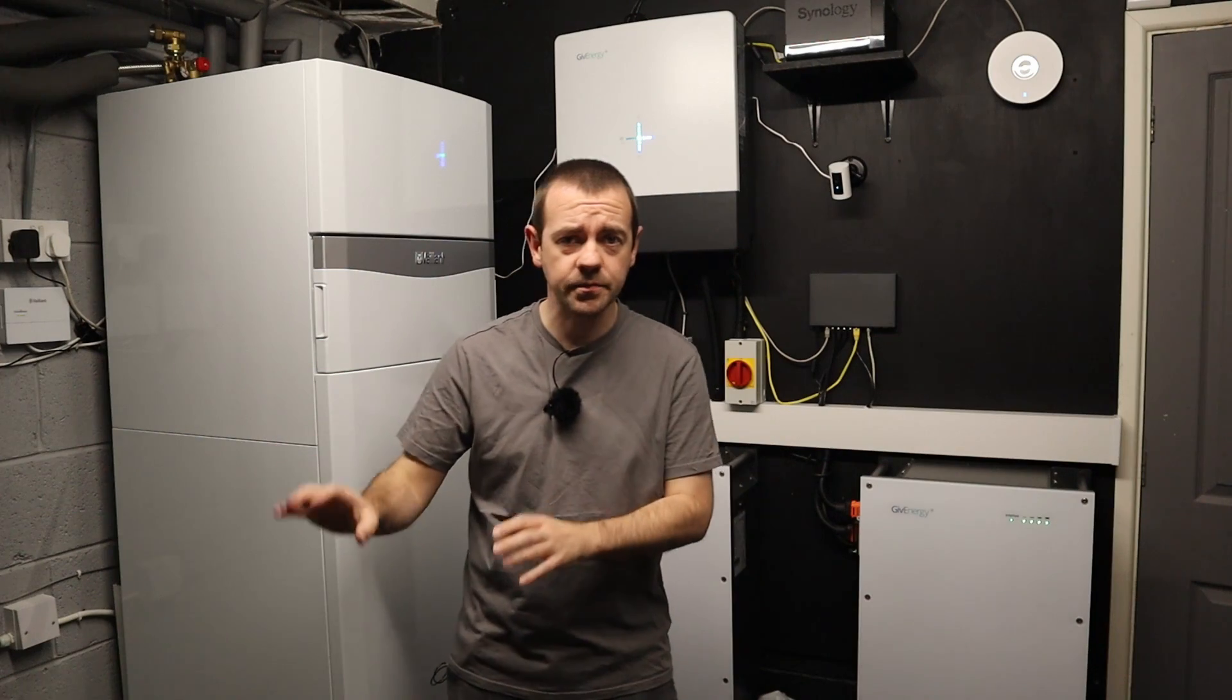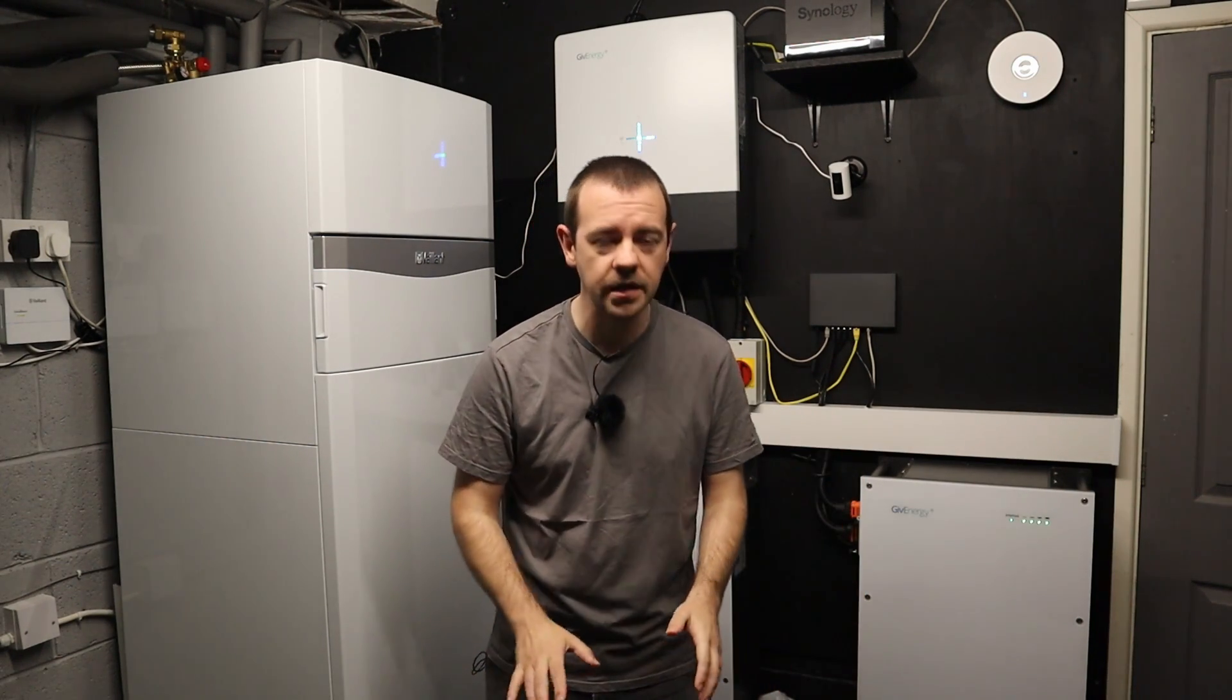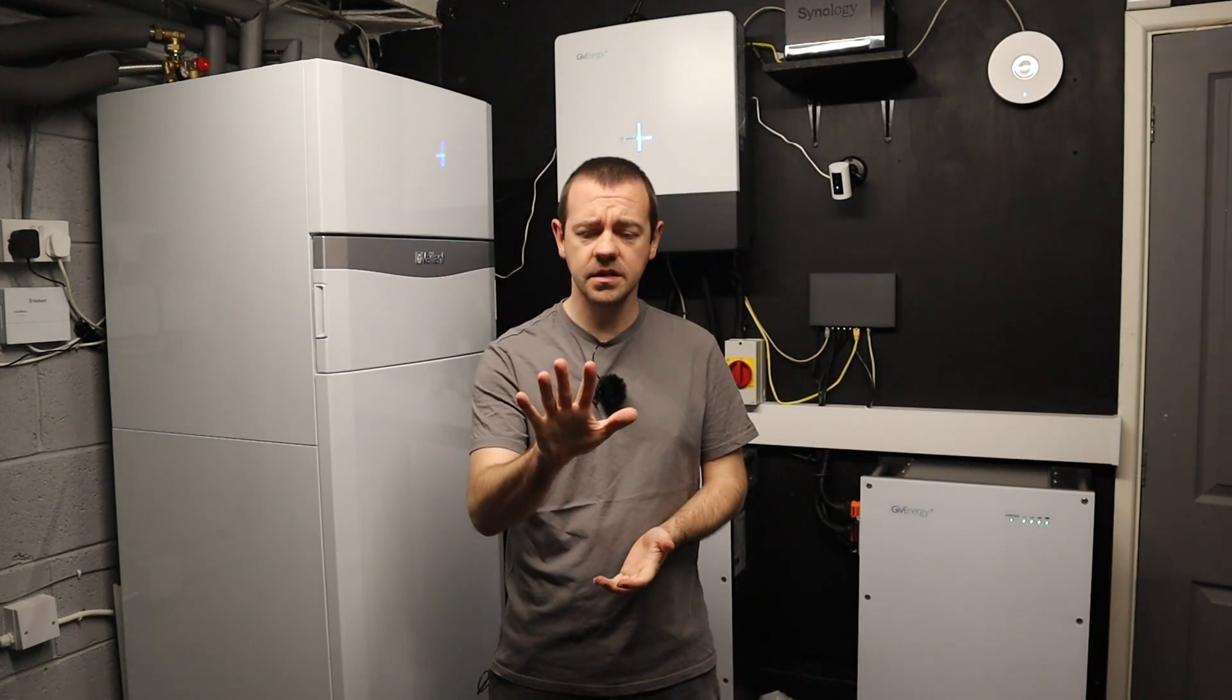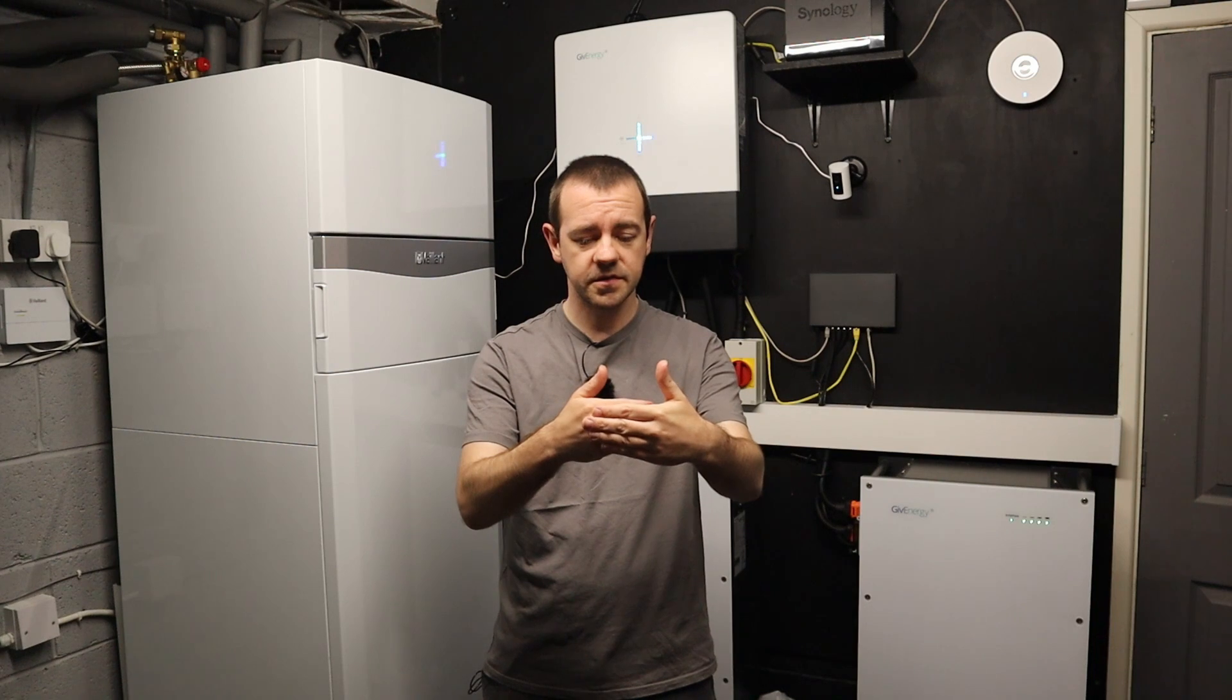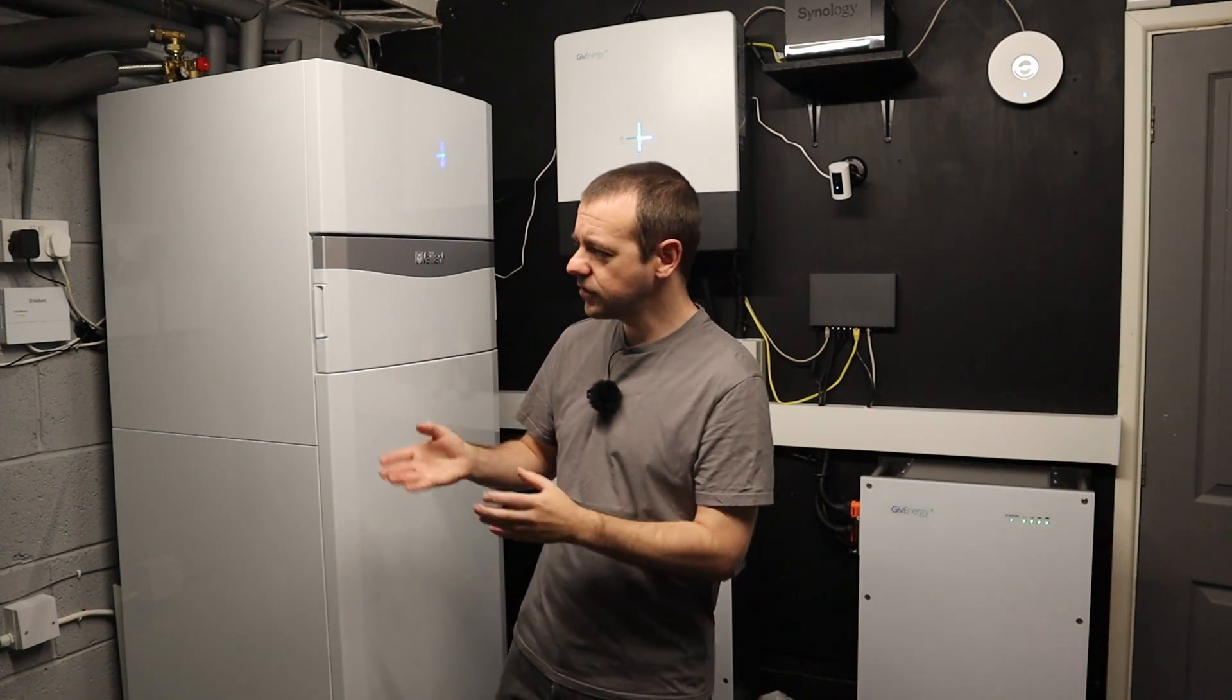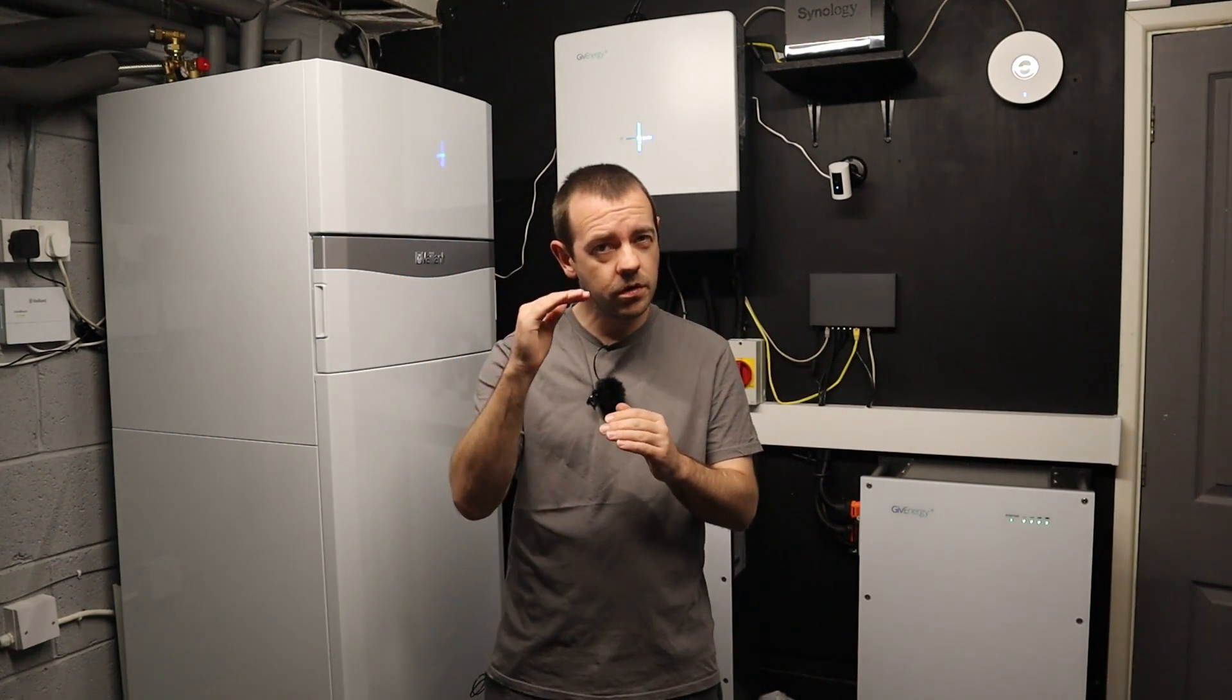The difference between a brand new gas boiler and a brand new heat pump is still considerable. And no, you don't need to replace all the radiators in your house. You don't need to have underfloor heating. That's another thing that won't go away. Again, this house is exactly the same as it was from when we had the gas boiler, with the exception of five radiators of thirteen that got replaced for just double panel ones instead of single. That's it. We could have just left it as it was, but we'd have had to run the radiators at a slightly higher temperature, and the heat pump would run at a slightly less efficient rating, which would cost me more money.